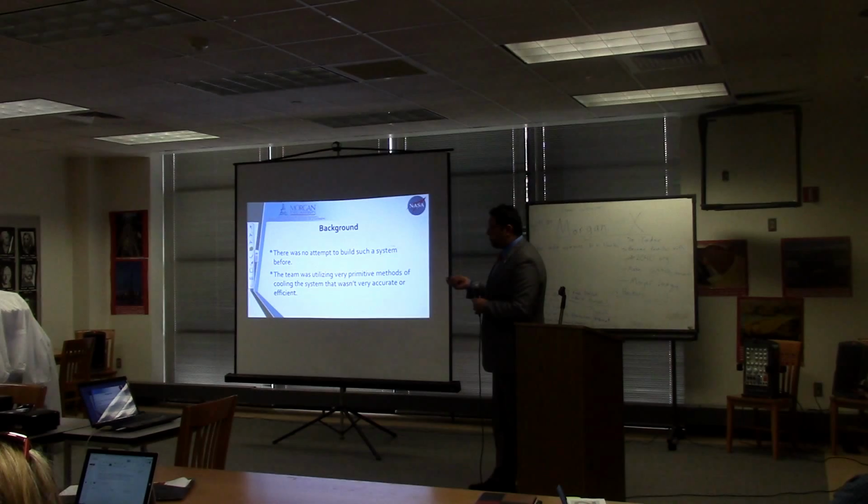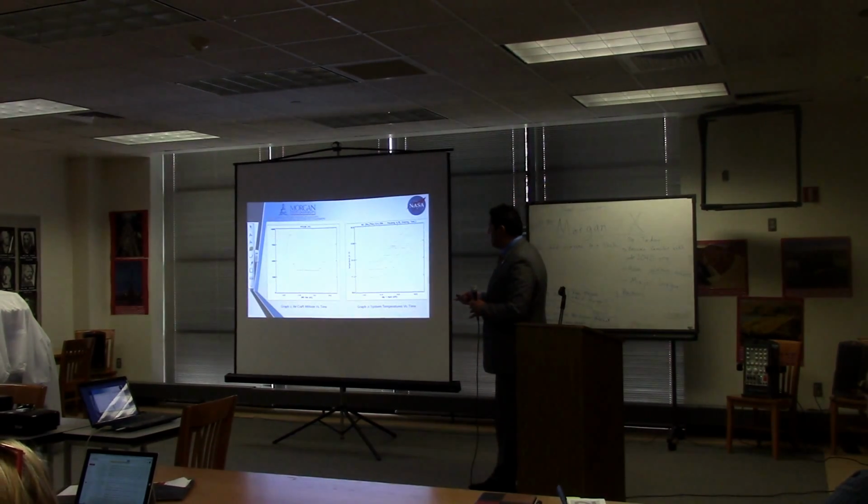For the background of this project, nobody had attempted that before. The team that was using the system, code 614 at NASA, were just using an air conditioner and pointing it towards the system to cool it down, and that wasn't very sufficient.